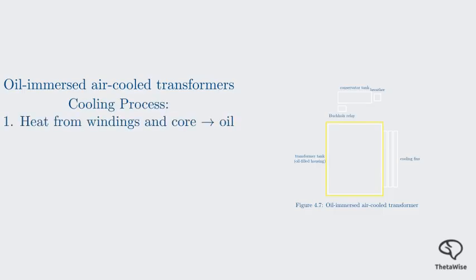Let's look at the most common type of oil-cooled transformer. This is the oil-immersed air-cooled transformer. Figure 4.7 provides a detailed diagram of such a transformer. Let's trace the cooling process. The process starts with the windings and core generating heat. Step 1. This heat is transferred to the transformer oil surrounding the components inside the tank. Step 2. As the oil gets hot, it becomes less dense, expands, and rises. This heated oil flows up into the cooling fins, which are visible on the sides of the transformer tank. Step 3.